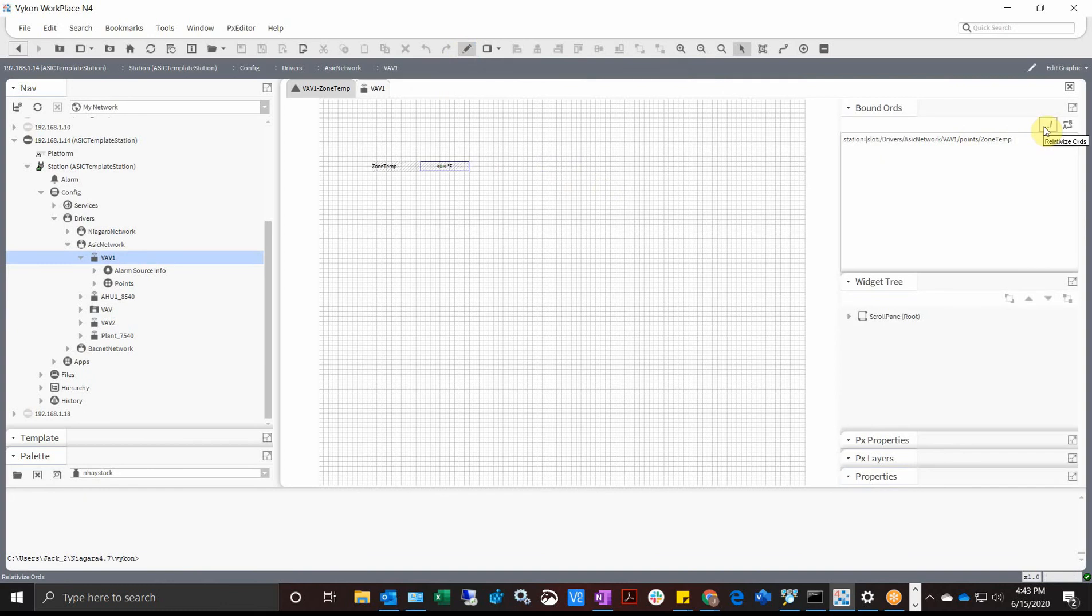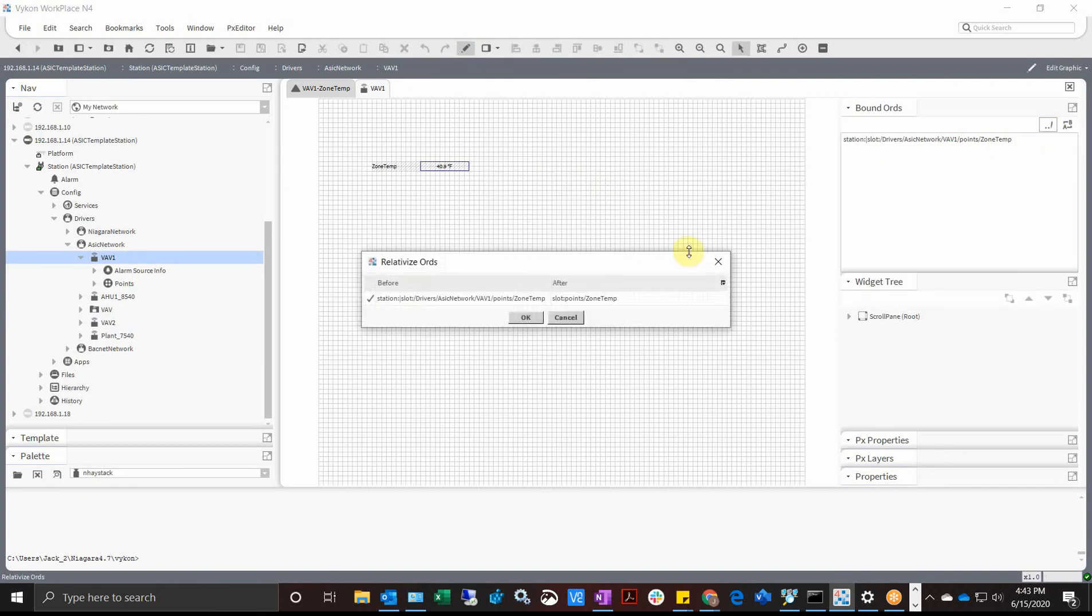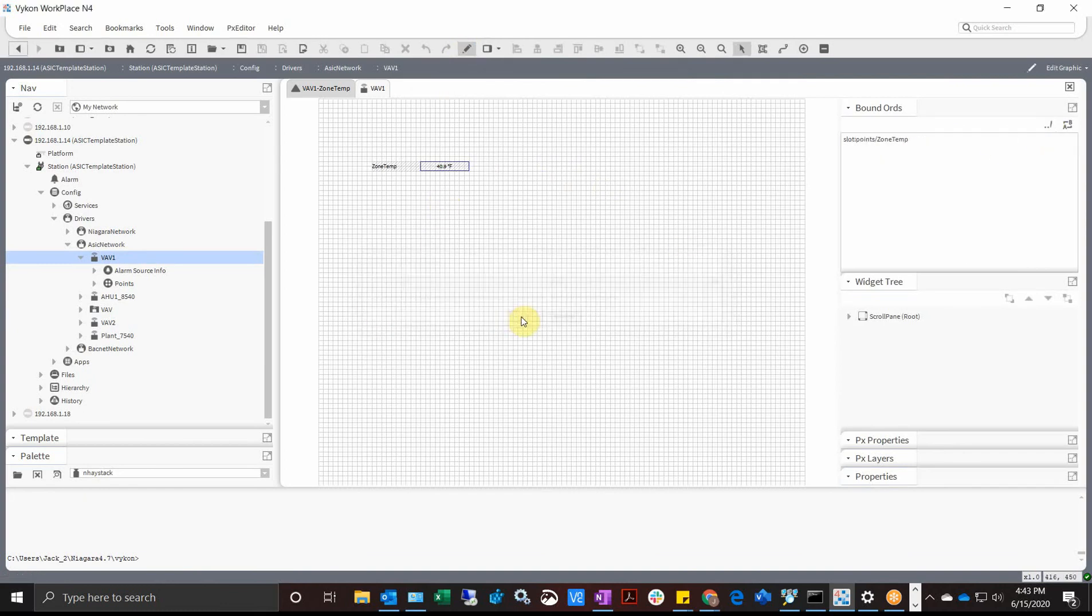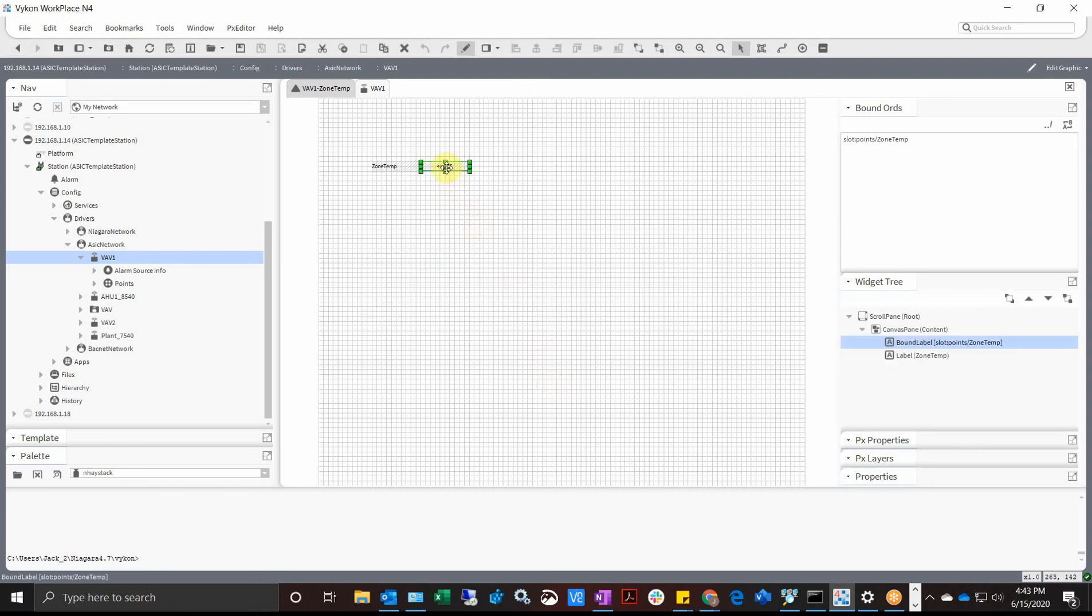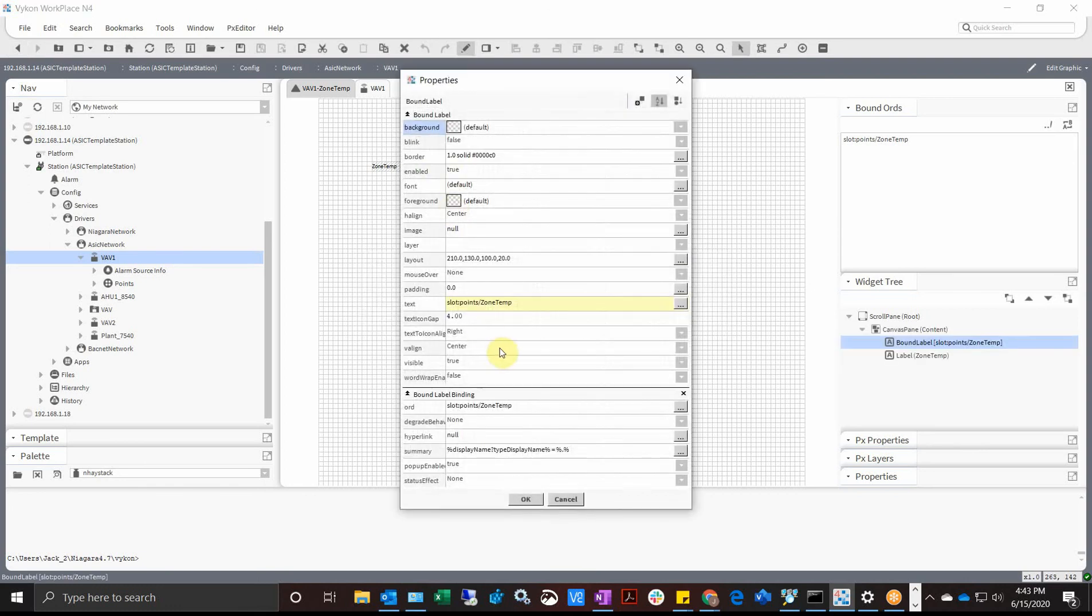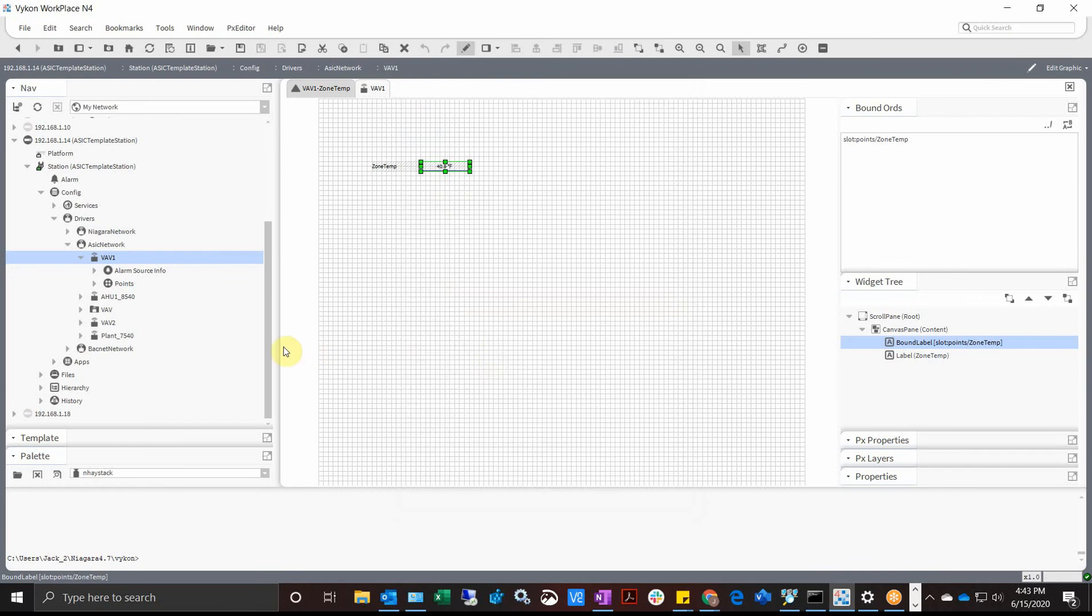So I'm going to go back there. All right, so edit, and there's a nice little button right here that says relativize ords. Click it and it'll give you a list of them. We only have one point so it's only going to do one. I'm going to hit okay, and if I double click on that now you'll see it's now relativized slot points zone temp, which is cool.